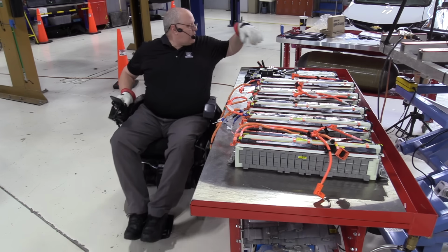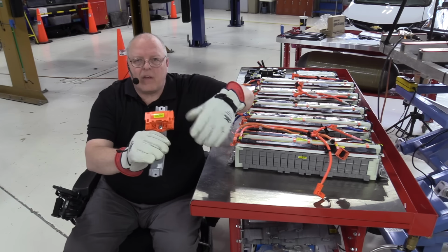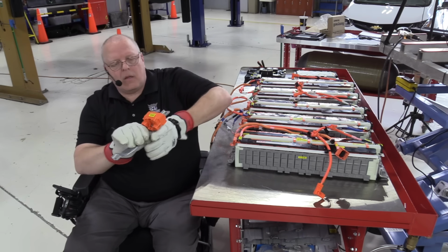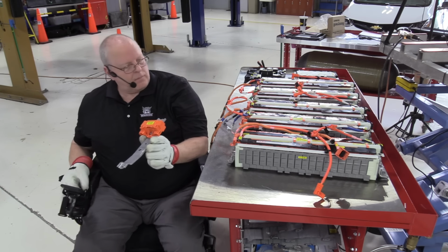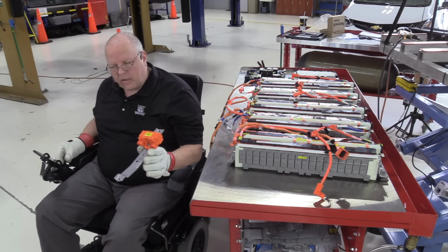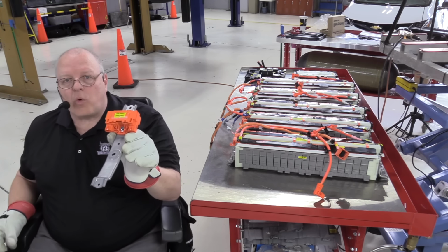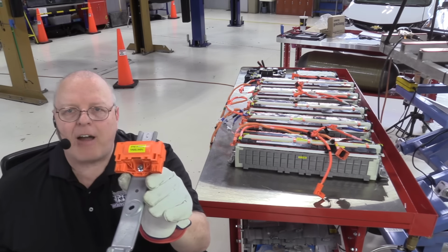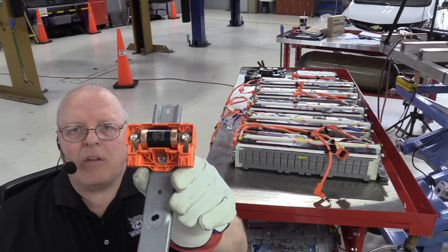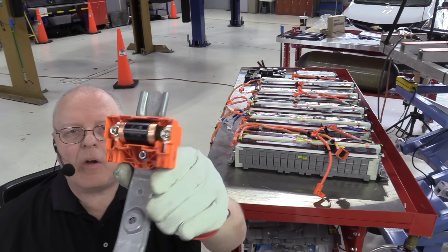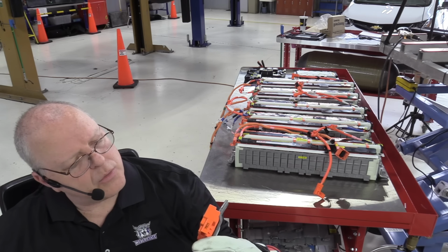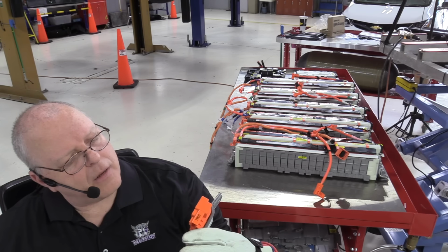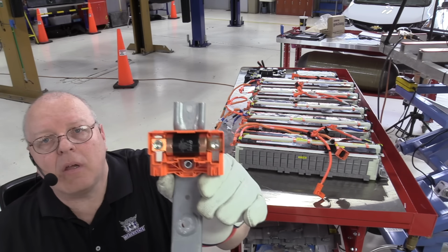Instead, they plug into the high voltage fuse, which connects battery stack number 4 to battery stack number 5. If I take the cover off of this, you can see the fuse in there. I believe it's a 250 amp fuse rated at 450 volts.